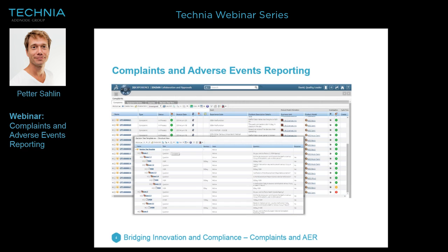Additionally, if we have complaints which are severe enough, assume that there is death involved with the event or the reported event for the complaint registered, or there is some severe injury related to that, then we need to file a report to the regulatory authorities. So these kind of rules we need to apply, and we need to have one set of rules for each and every market on which we are active.